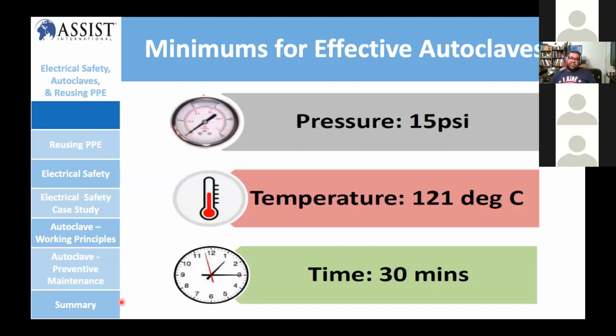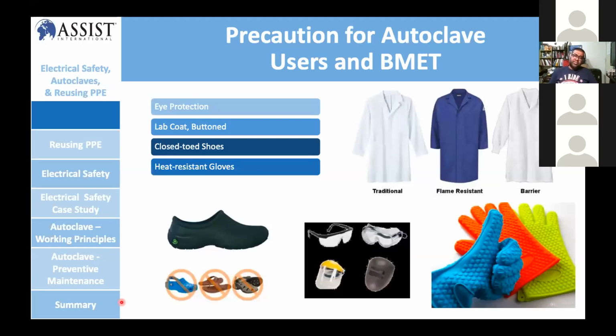When you talk about autoclaves, you always have to remember that to get good performance you need a minimum of 15 psi, and temperature and time. These three play a very important role. If one of them fails, you're not going to get proper sterilization. So always remember that. When you're working with an autoclave, as a BMET, always remember PPE is very important: eye protection, lab coat, closed-toe shoes, and gloves, because you're dealing with heavy items and wet surfaces.